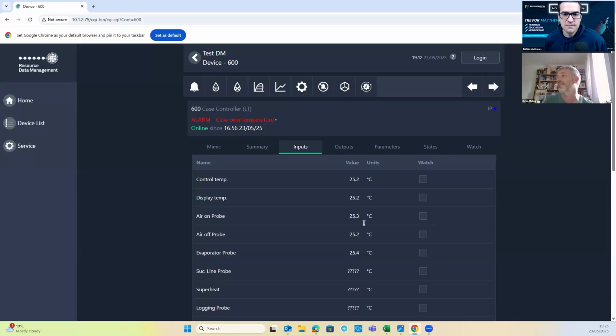If you set it 60-40, it will take 60% of the air on and 40% of the air off, and it'll work out the value. You set it 100%, in RDM's case, it will read all air on, right? If you set it to 0, it will read all air off. And so air on is return air. Just wanted to clarify that, right? So we get the return air on. That's the air going onto the coil. Air off is the discharge or the supply getting blown out. For an example, that's it.